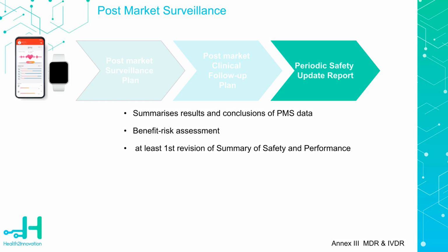Manufacturers of Class 2A, 2B, and Class 3 devices, as well as custom-made devices, are required to prepare and update PSURs regularly. This report summarizes the results and conclusions from the PMS data, including any corrective actions taken, findings from post-market clinical follow-up activities, and an assessment of the benefit-risk balance.